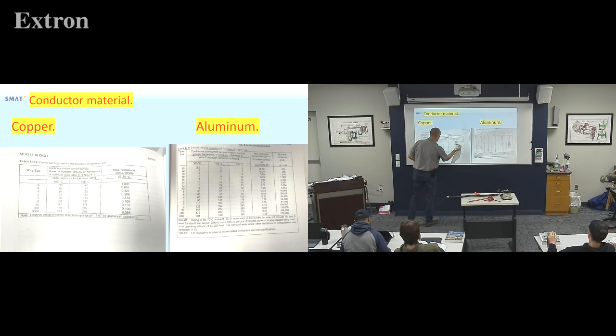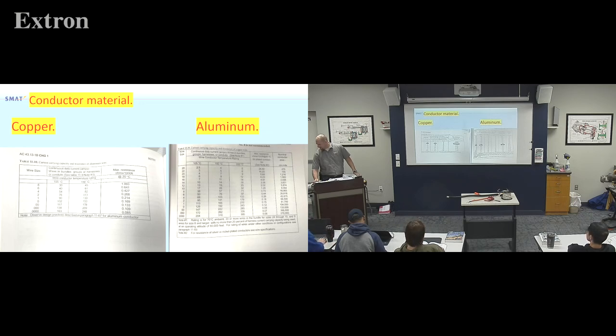If you come all the way down here, it'll say it should be 0.427 ohms per 1,000 feet. So that's pretty general for aluminum. If we go to the copper one, 6 gauge, so the same number of circular mils, the same area, if you will, we get 50 amps. So I can actually carry a little bit more load, and 0.44 is what I'm reading there for ohms. So similar ohms. It actually says it's slightly more ohms if I'm looking at that right.